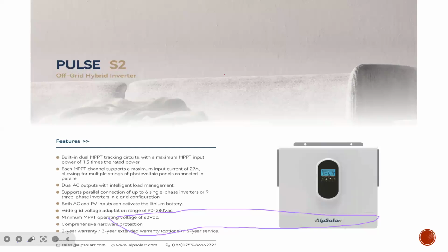So each of the MPPT channels supports a maximum input current of 27 amps, allowing for multiple strings of photovoltaic panels connected in parallel. What that is saying is that it does not only give you PV input power of 16,500 alone, it also gives you enough PV input current, which is 27 amps, which gives you the opportunity to maximize that power. So with the PV input voltage of 500 volts and 27 amps, it gives you the opportunity to arrange your panels both in series and parallel to maximize the PV input power accommodation given on this inverter.